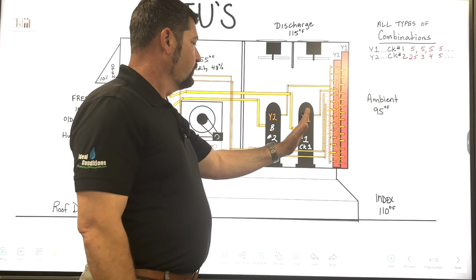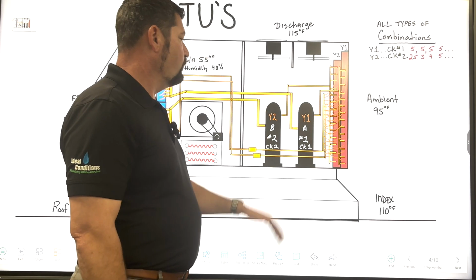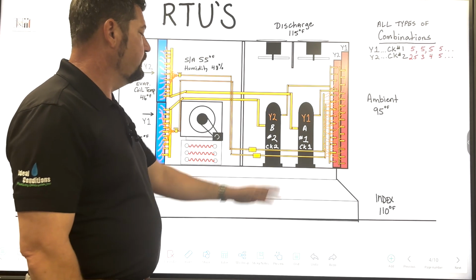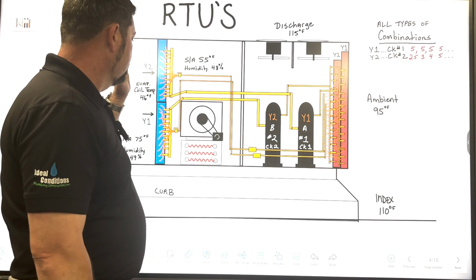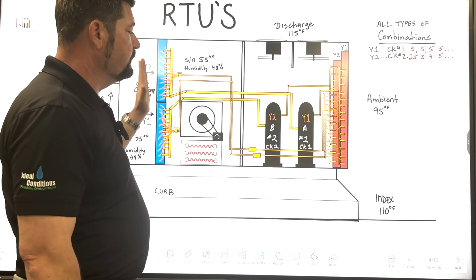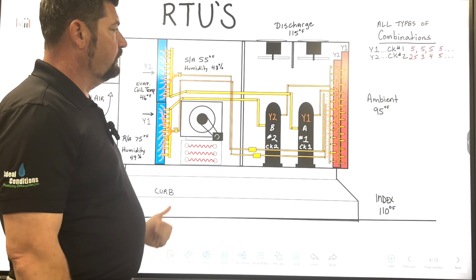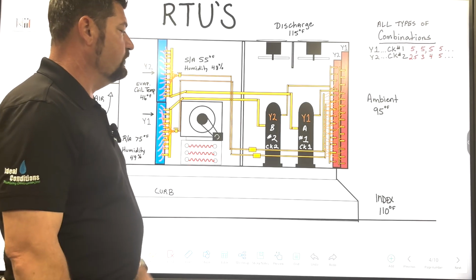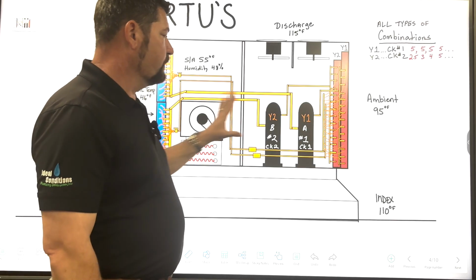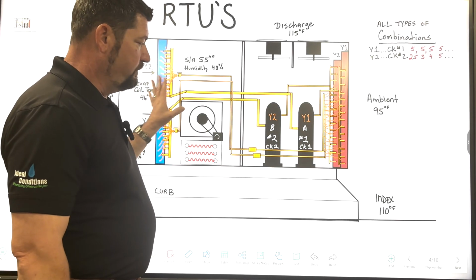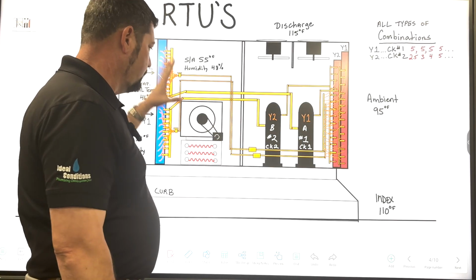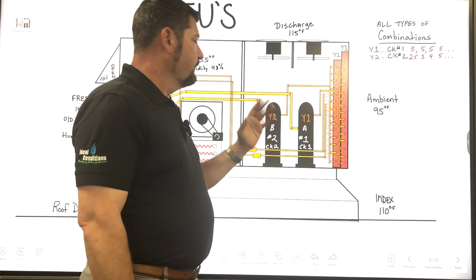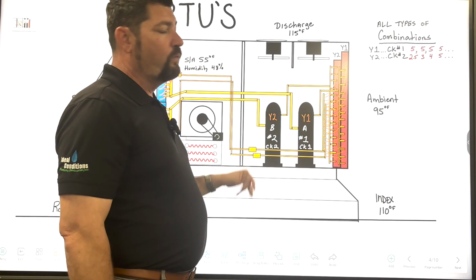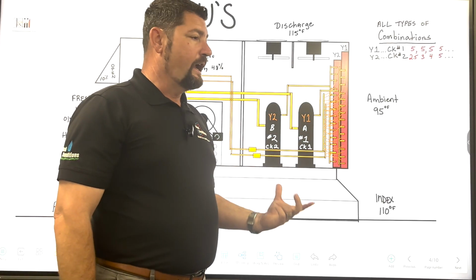But if you're running wide open, full demand, Y1 and Y2, A and B, 1 and 2, circuit 1, circuit 2, then you're going to have too much demand and you're going to shorten that cycle, and that will cause a humidity issue.